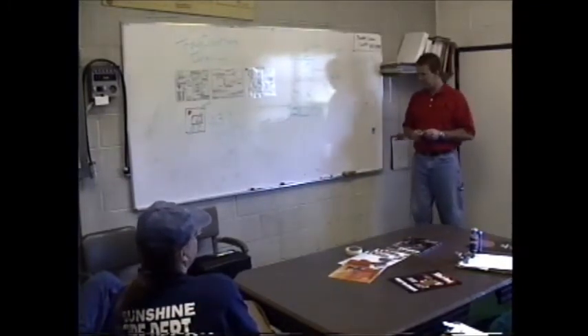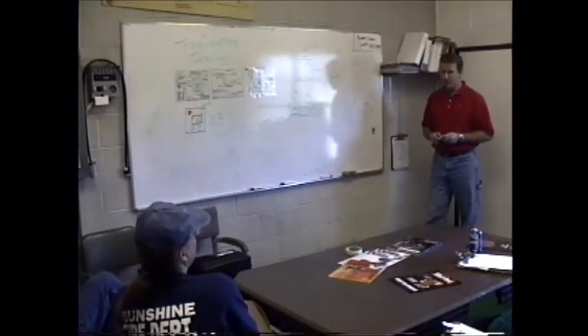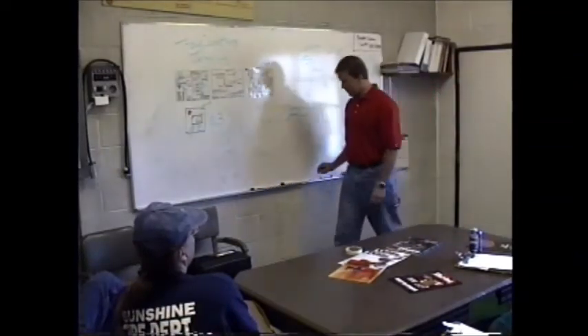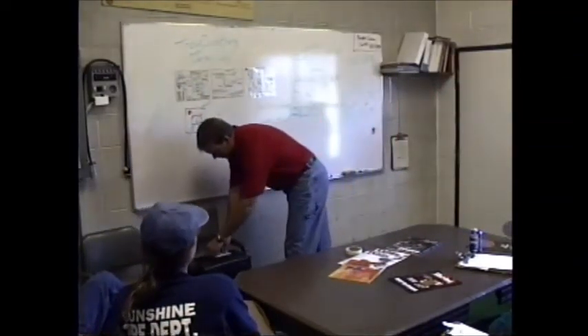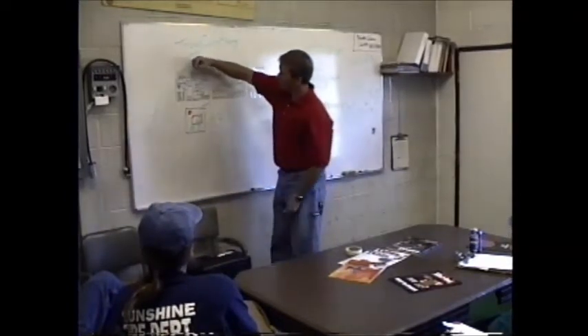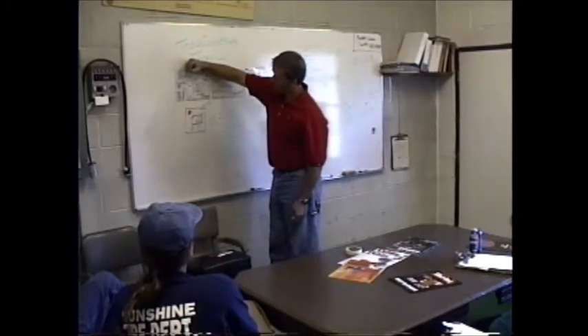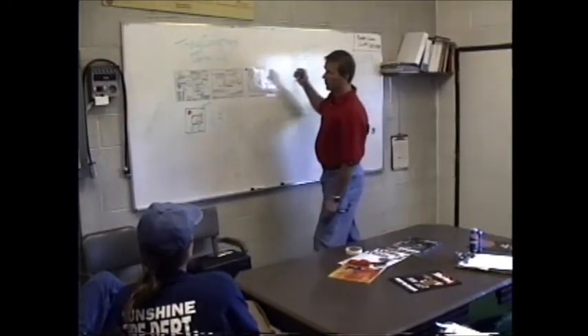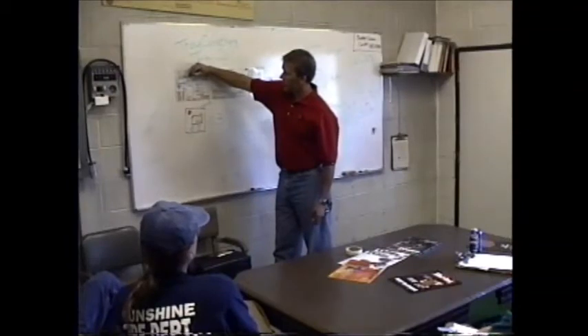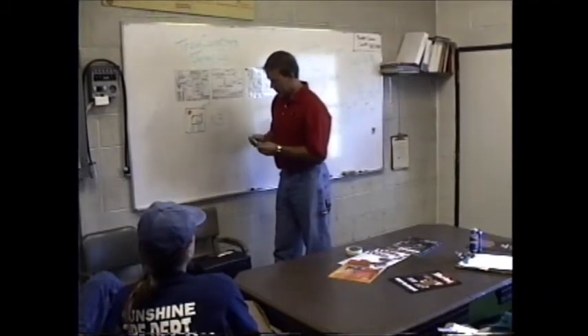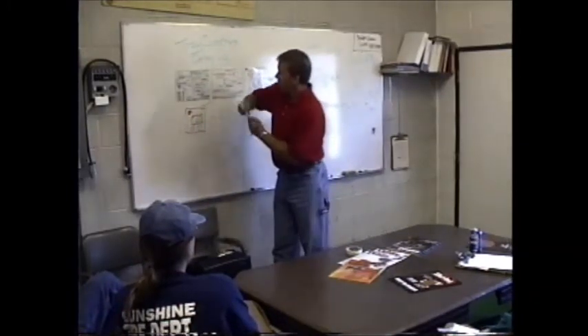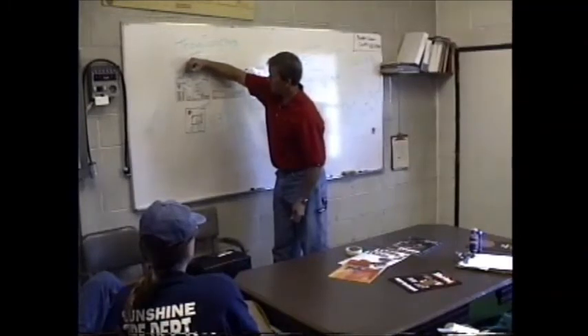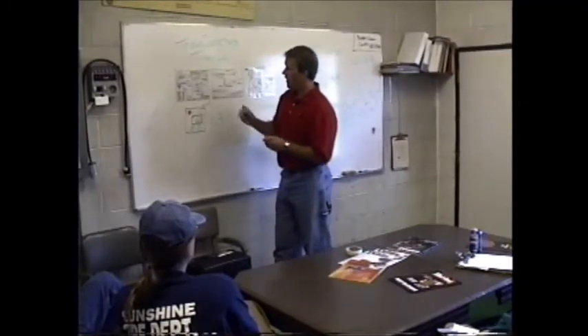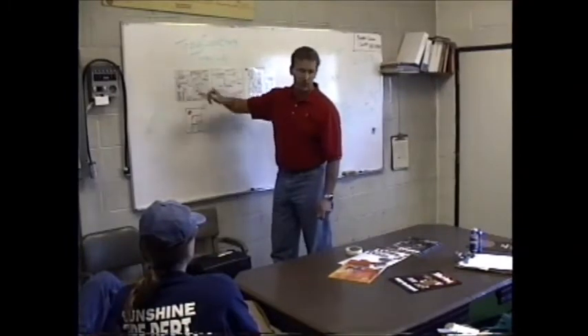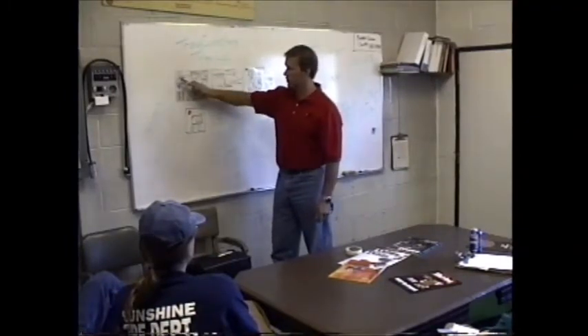Troy, on your deck gun, do you have a mixer because you don't have the hose length? Yep, you do. Okay. That's why on the deck gun, glad you brought that up. As that foam water solution goes through the valve for the deck gun, here's your control valve that'll be on your pump panel for giving your water to your deck gun. It's going to go through that check valve so that the air can't get back into here. And then the water and foam is going to get to here. Your air is going to come in through that ball valve on your pump panel, it's going to mix with the water and foam, and the first thing that it runs into before it gets to the main standpipe riser that goes to the deck gun is this motionless mixer.